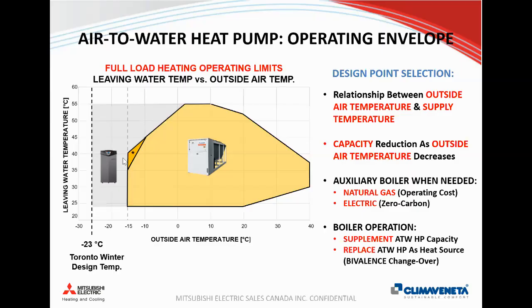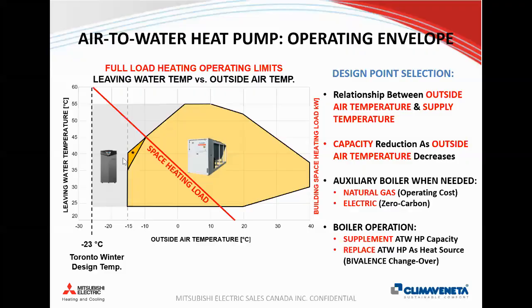So again, if we look at the design temperature for Toronto at -23, this is the same diagram with the heat pump supply temperature, but also on the right axis now, we're just looking at the building space heating load. Because the other thing to keep in mind with heating systems generally is that your space heating load is going to be at 100% for the design day conditions. So in this example, -23 degrees Celsius in Toronto, that's where at -23, we have 100% of our heating load.